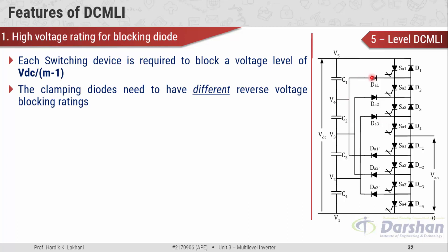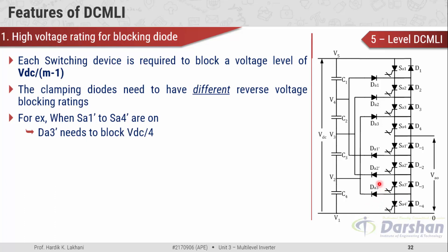The clamping diodes need to have different reverse voltage blocking ratings. For example, when SA1' through SA4' are on, the clamping diode DA3' needs to block VDC/4. This is because its anode terminal gets connected to node V1 and its cathode is connected to V2, so DA3' appears in parallel with capacitor C4, and the voltage drop across C4 is VDC/4. Therefore, DA3' must block a voltage of VDC/4.